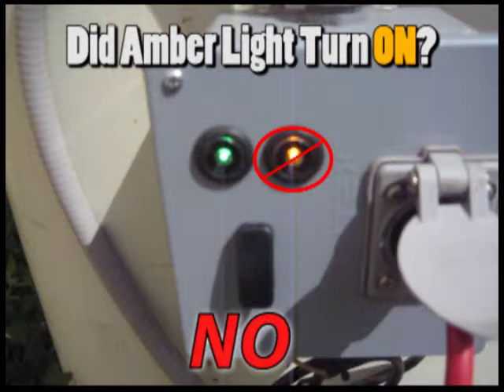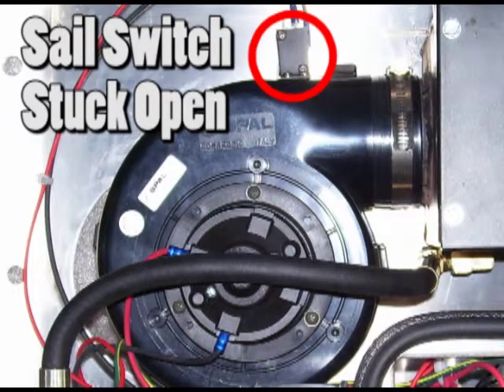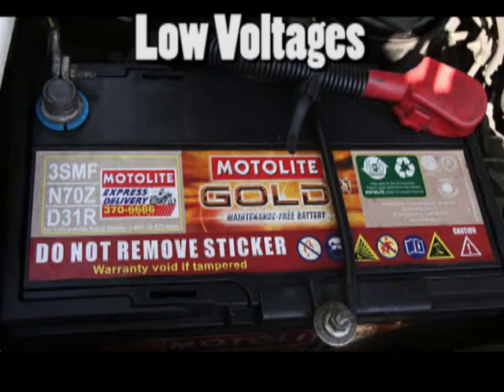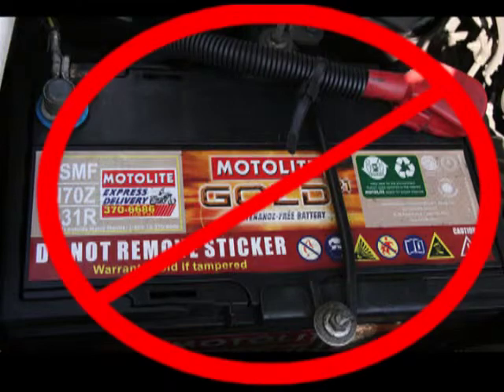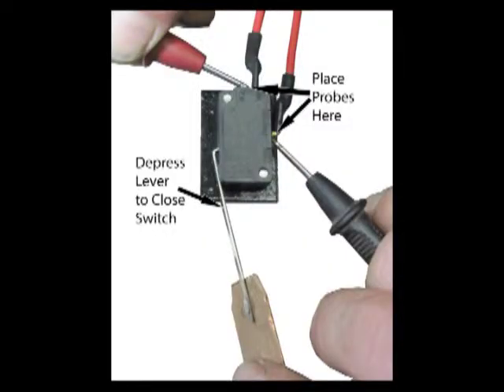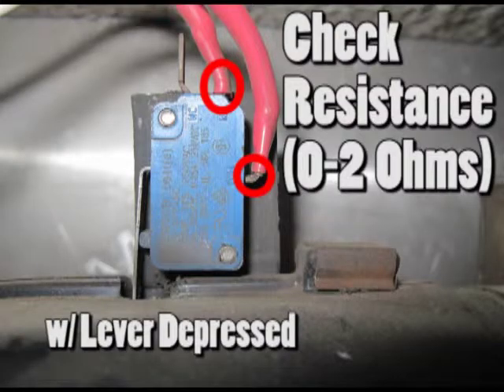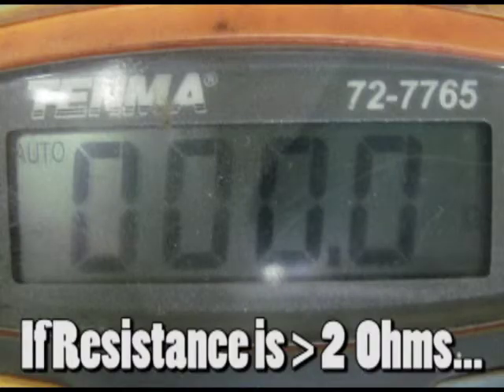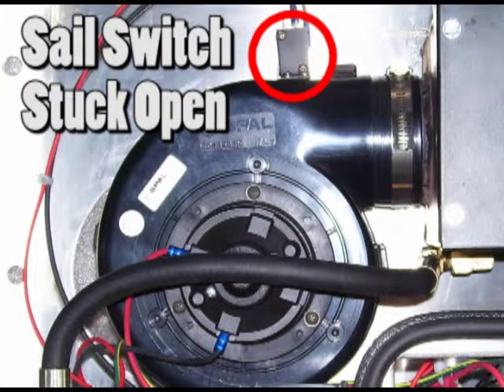If the amber indicator light on the control box did not turn on when depressing the activation lever of the sail switch, this indicates that the sail switch is stuck open or the voltage to the heater is very low. With the power to the heater off, check the resistance between the 2 terminals on the sail switch with the activation lever depressed. Or on models with 3 terminals, the wire should be attached to the 2 terminals on the right side. Place your probes on these 2 terminals while depressing the activation lever. If the resistance measurement is anything outside the 0 to 2 ohm range, the sail switch is either stuck open or bad.